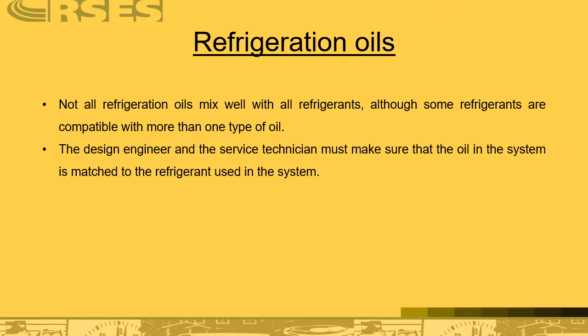Please note that not all refrigerant oils mix well with refrigerants, although some refrigerants are compatible with more than one type of oil. The design engineer and the service technician must make sure that the oil in the system is matched to the refrigerant for use in the system.